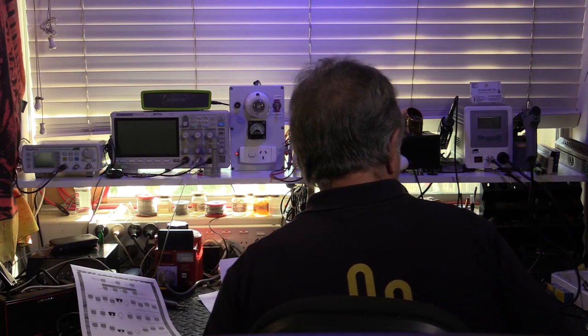Is it that easy? No, it's not. Because we also know that I squared R is equivalent to the power loss in that transformer, and that will appear as heat. We also know that heat is bad for a transformer, because around each one of those copper wires, of which there are hundreds of turns, there is insulating enamel, and that will soften as the temperature goes up.